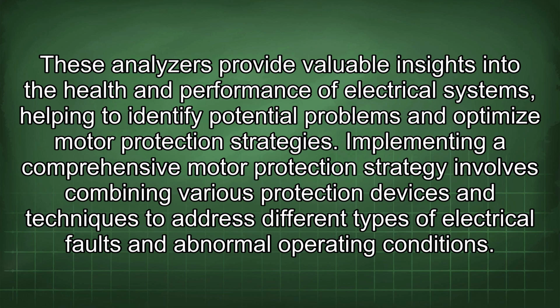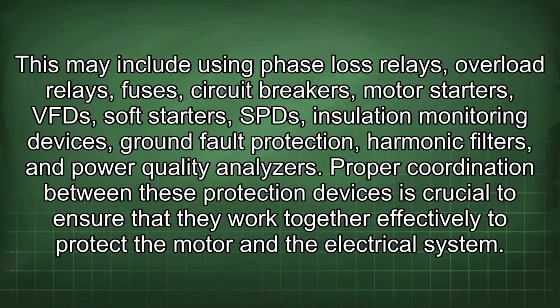Implementing a comprehensive motor protection strategy involves combining various protection devices and techniques to address different types of electrical faults and abnormal operating conditions. This may include using phase loss relays, overload relays, fuses, circuit breakers, motor starters, VFDs, soft starters, SPDs, insulation monitoring devices, ground fault protection, harmonic filters, and power quality analyzers.